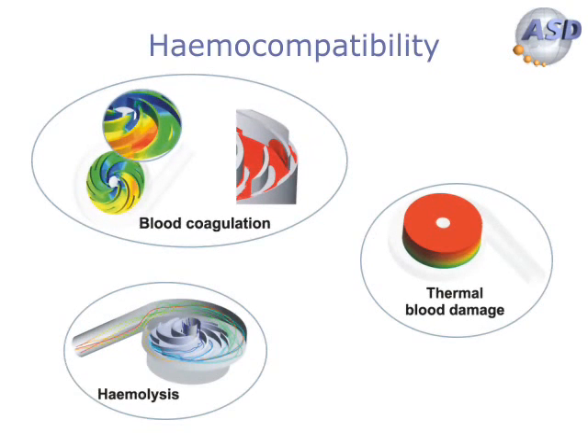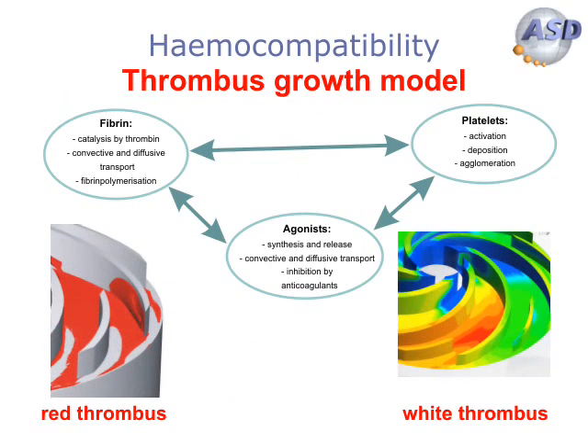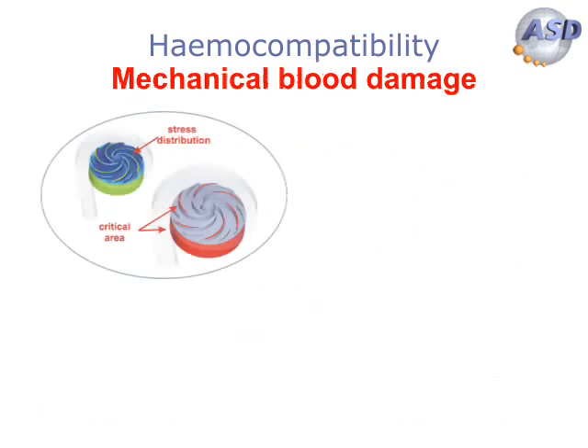ASD has special know-how and long-term experience in the modeling, simulation and assessment of blood pumps regarding blood damage and thrombosis. In a simulation model for thrombus growth, for example, the complex biochemical interactions involved in the activation of platelets and the subsequent formation of a white or red thrombus can be predicted.